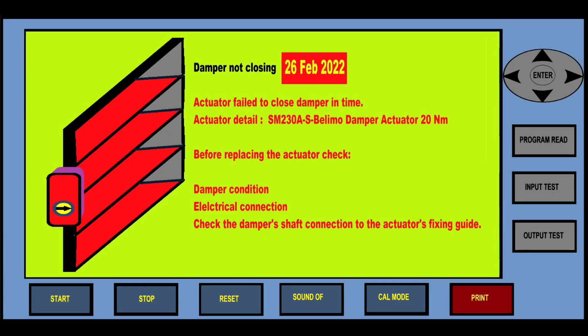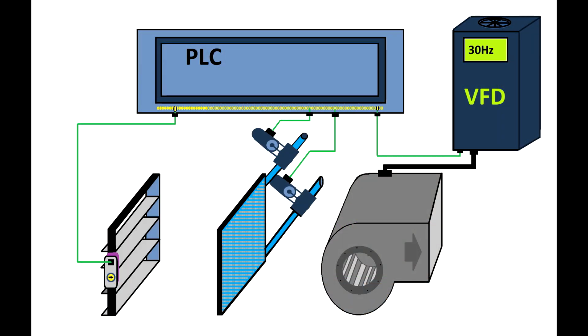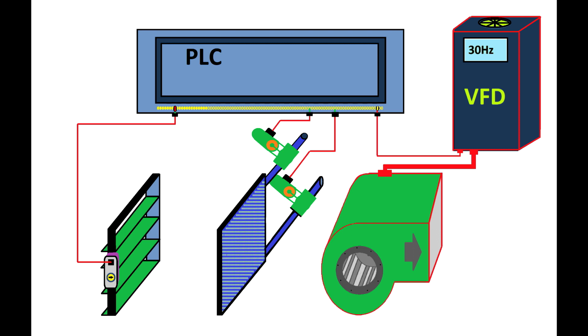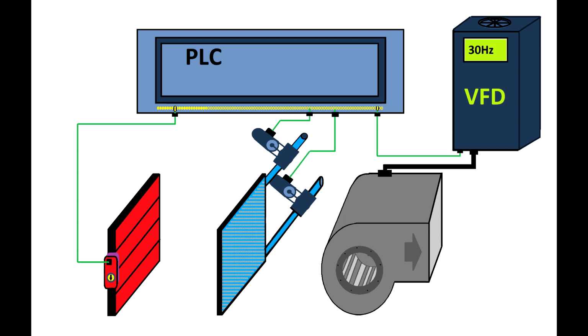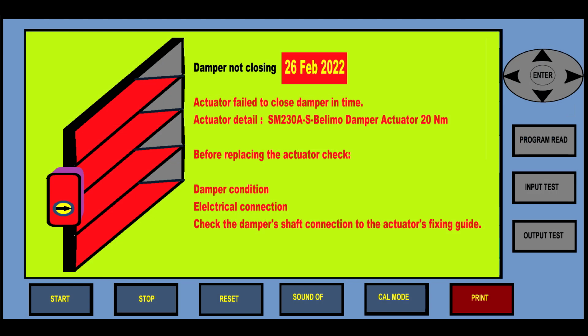If you have a faulty damper, the HMI will tell you what to do. So look into this video, you'll see a damper that is opening and is sending an instruction to the PLC. That's an instruction to the variable speed drive, and it will turn the motor on and the cooling heat exchanger, like you'll see in this picture. And if there is a fault on a damper and the damper does not open, it will instruct the PLC to hold off the motor and the heat exchanger. You cannot run the cooling heat exchanger. You don't want to freeze it up because the air is not passing by.